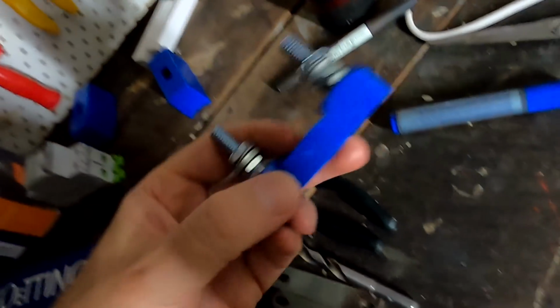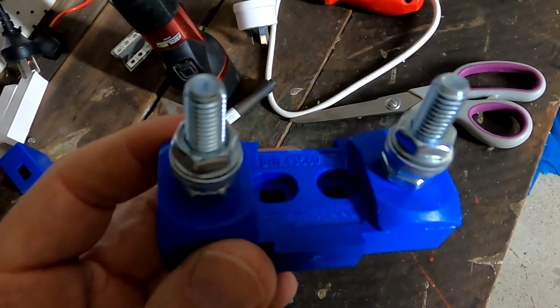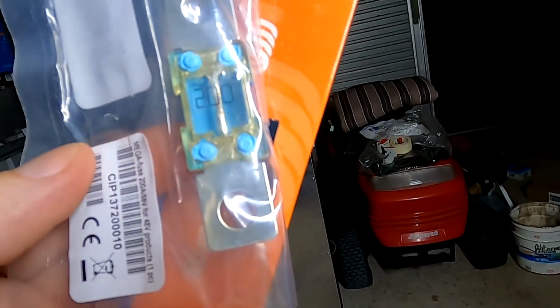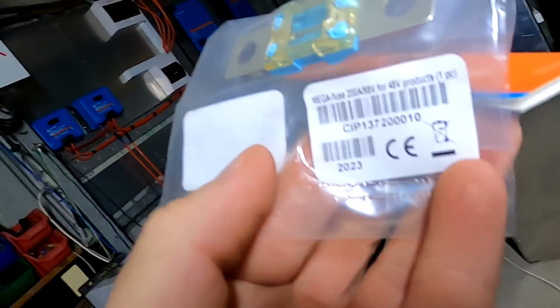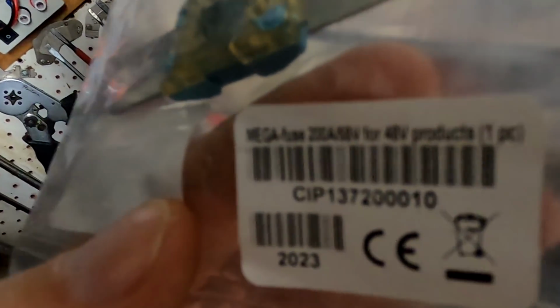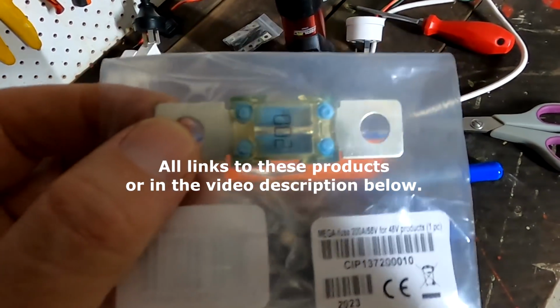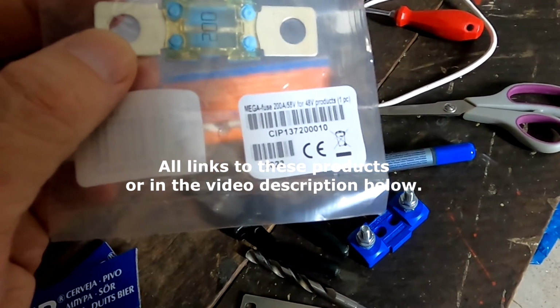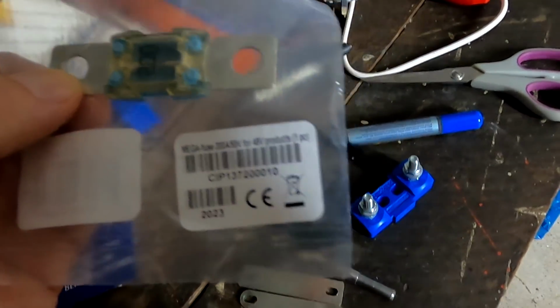So what to do? Well, most people use fuses, right? I've already got a Victron mega fuse holder here with M8 studs and a 200 amp fuse, there. It's a 200 amp 48 volt mega fuse. Actually, it's a 58 volt fuse for 48 volt products. That's what it says over here. And 58 volt is important because even when the fuse has gone, you don't want to have an arc in between. Hence they are producing these mega fuses especially for 48 volts. There are also some for 24 volt. So you need to pay attention if you buy them. They need to be rated for your system voltage.